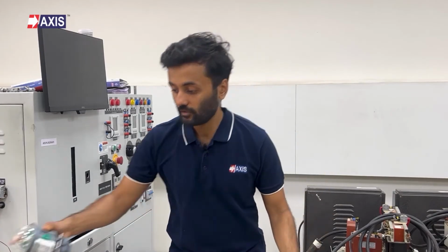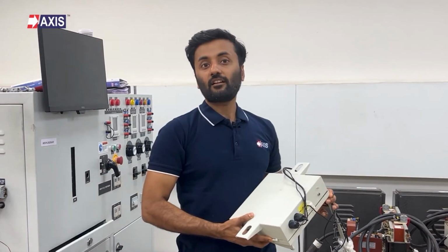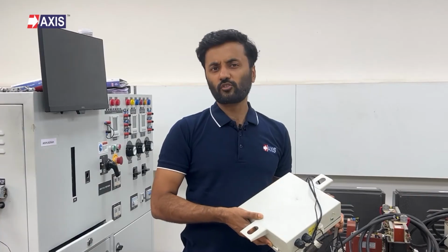Now let's explore the communicable type of FPI. These not only alarm on site but also transmit data to the SCADA center via a data collection unit over GSM/GPRS networks. This is what a data collection unit looks like, also called a DCU. Communicable FPIs are effective in all kinds of terrain because it is not dependent only on visual inspection. The operations and maintenance team has a clear indication on the location of the fault and does not need to waste time on finding it.